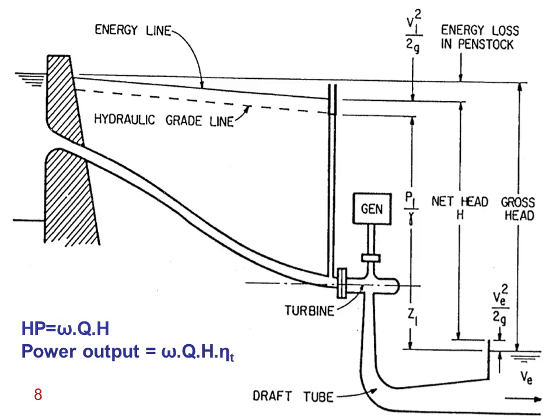Here is a hydraulic sketch for a dam with upstream on the left and downstream on the right. There is a tunnel that transmits water from upstream through the dam to the turbine and then downstream. The difference between upstream and downstream levels is called the gross head. If you have a long pipeline transmitting water from upstream to the turbine and a draft tube taking water from the turbine to downstream, you have energy losses due to friction and other losses along these piping systems.